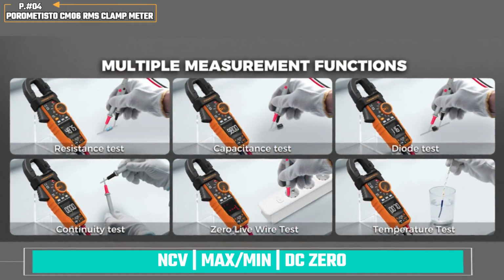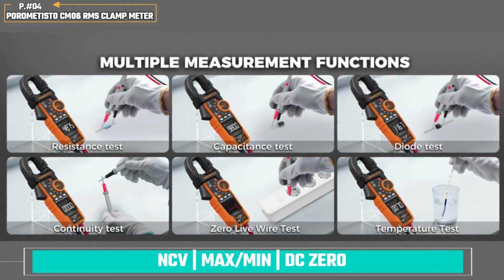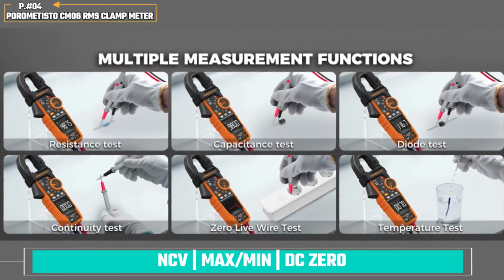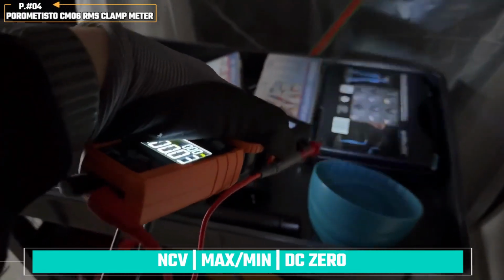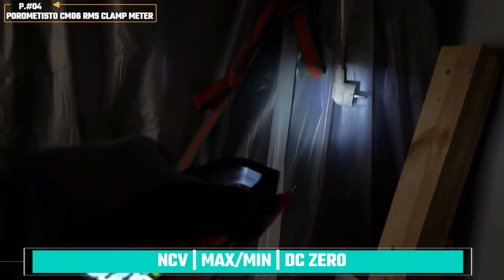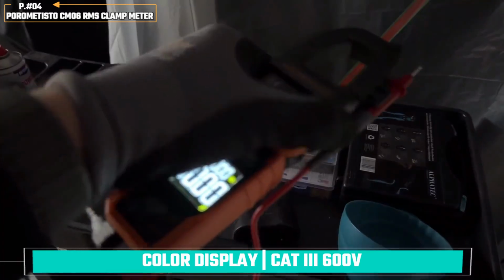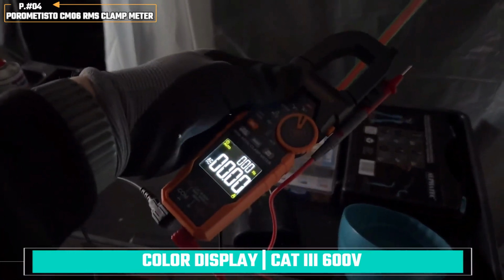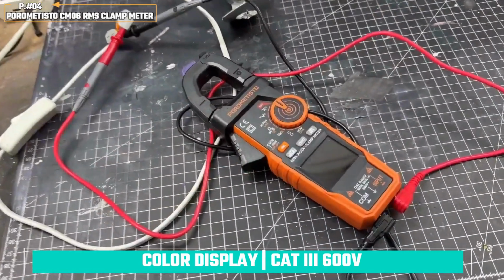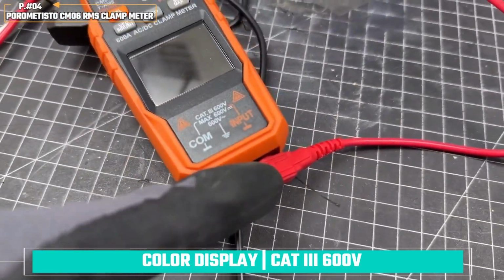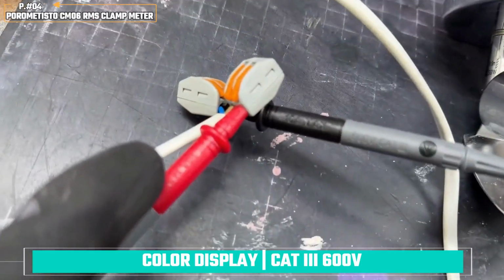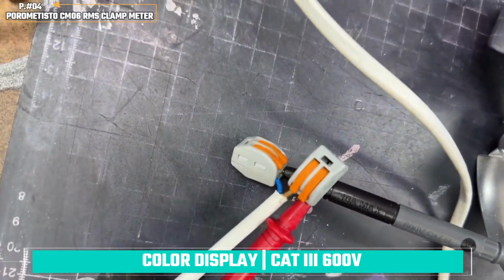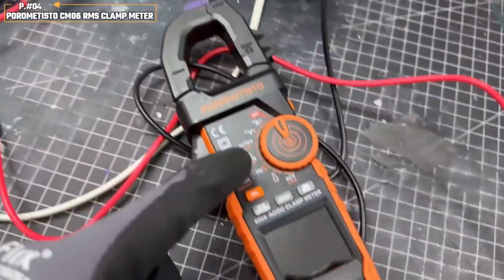It also measures resistance, capacitance, frequency, duty cycle, temperature, continuity, and diodes. NCV detection provides a quick warning of nearby AC voltage, while max/min, data hold, and DC zeroing support more controlled testing. The color display and built-in flashlight improve visibility around dark panels. The standard CM06 carries a CAT III 600-volt rating and includes test leads, a thermocouple, batteries, a screwdriver, and a storage case.